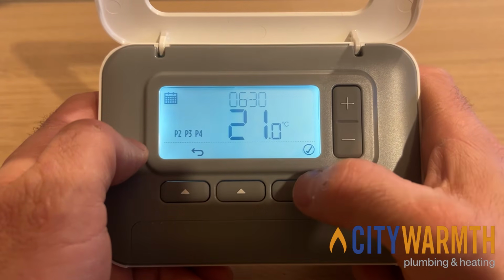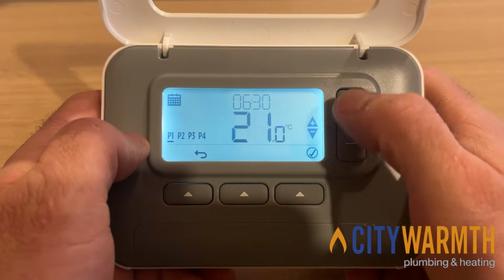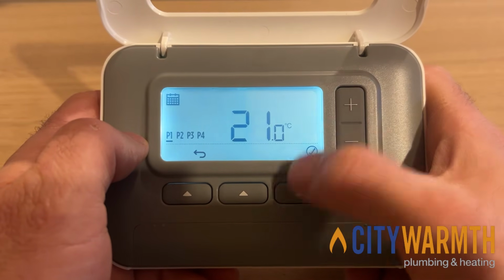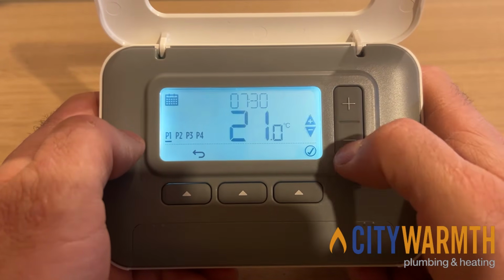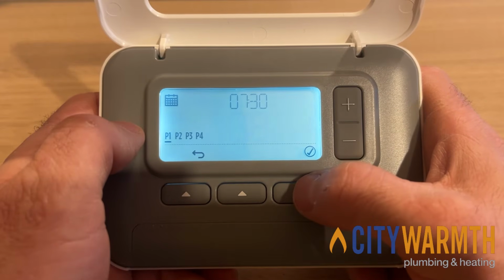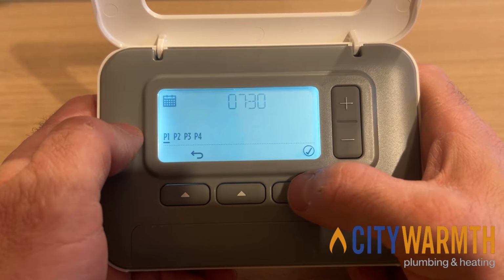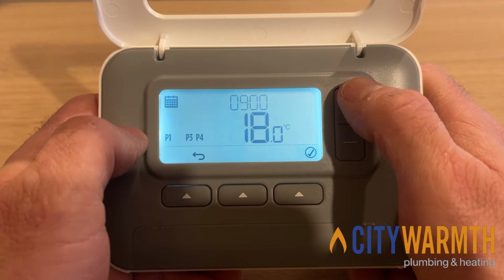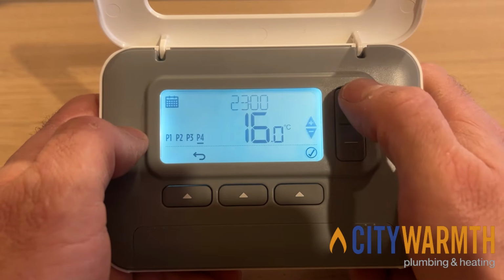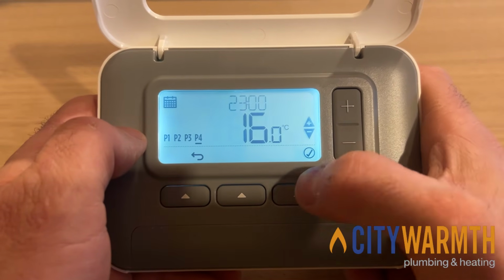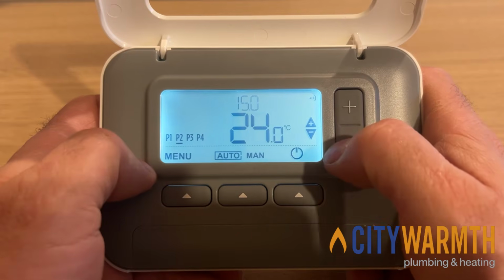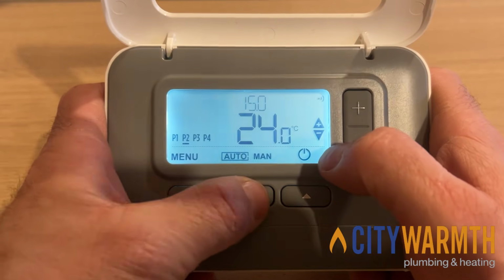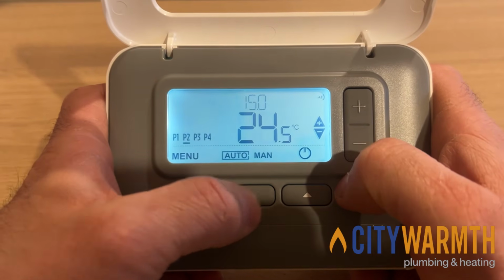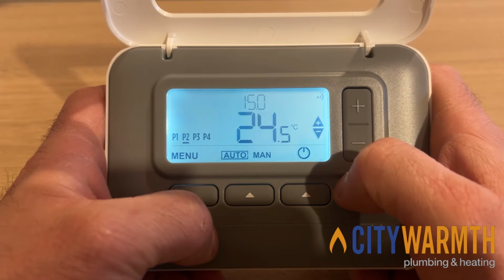Saturday, Sunday, set the program the same way. P1, time and temperature, not on and off, time and temperature. I want the house to be 21 degrees at 7:30. It will come on at about 6:30, 7 o'clock to bring the house up to that temperature for that time. And you toggle through the rest of the settings for Saturday and Sunday in the same way. What temperature do you want the house at what time of day? When you are done with all your settings, it takes you back to the main control display. Manual to override, automatic to let the programmer run the program that we have just put in.